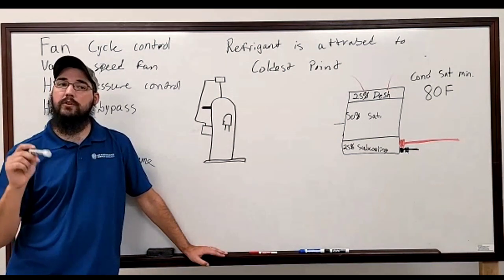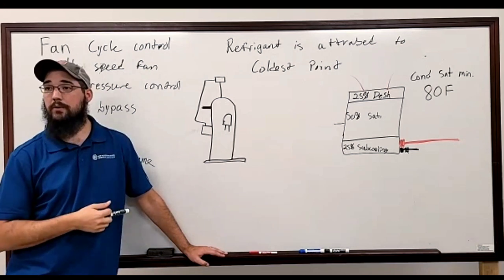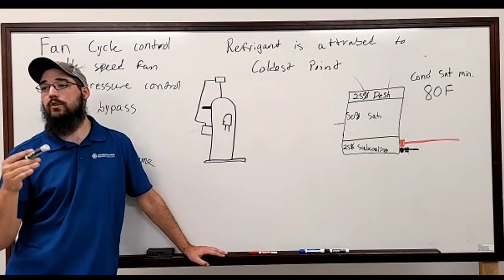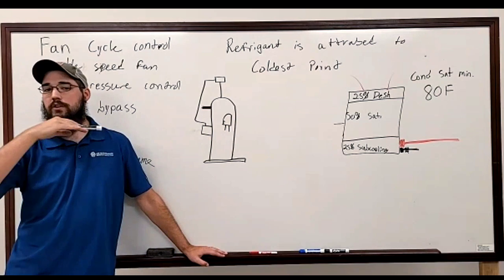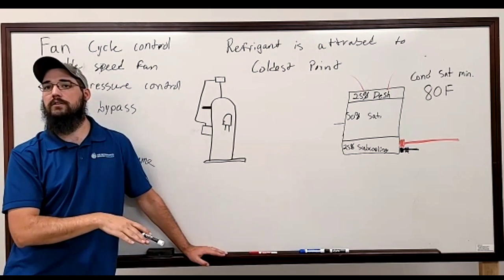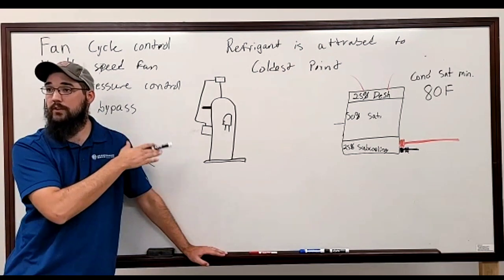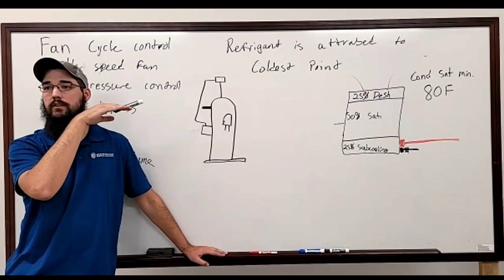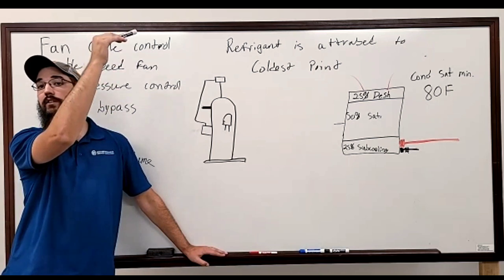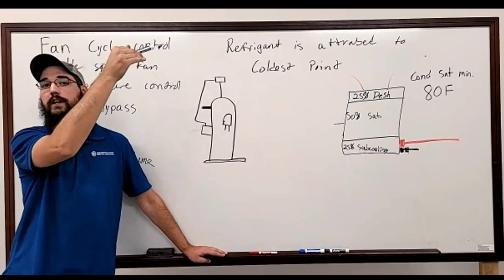What is the logic loop that's controlling discharge air temp on an RTU? Or if this was, say, a chiller, for example, it's the logic in the controller controlling leaving water temp, right? So we'll stick with an RTU. Your discharge air set point is still 55. You get down to 54. You're beginning to overcool. Okay, we need to cycle down. Well, instead of killing the compressor, unload one compressor, and we get back to 55. And then once we get back to 56 degrees of supply air, we see, okay, we're starting to go up. Well, let's reload that compressor.